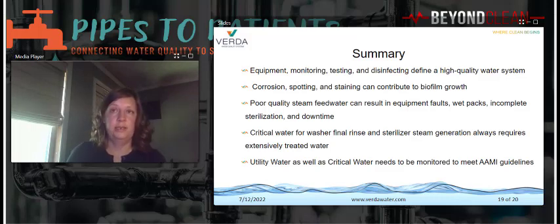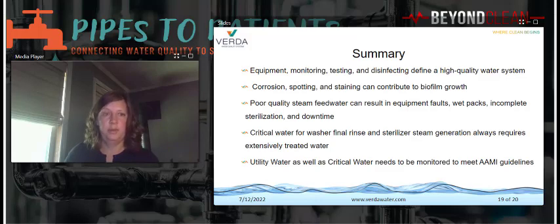Water is the main ingredient of getting dirty instruments clean. Poor water quality can cause various problems with equipment, with instrument life, and ultimately with patient care. Critical water always requires extensively treated water and needs to be monitored to meet those guidelines. However, when talking about the SPD, most people are really focused on purified water or the critical water, and not a lot of talk about utility water. But the utility water quality could cause problems in the cleaning and sterilization process if it's not handled properly.